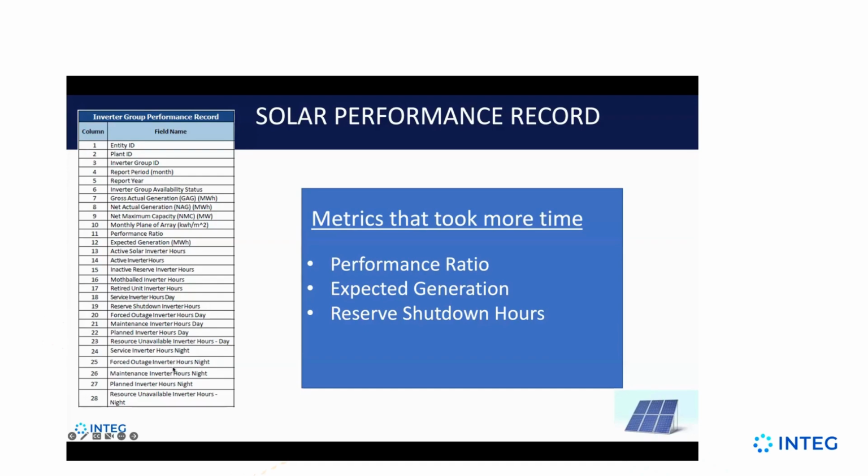A lot of folks, when they're doing their work, they're only looking at the outages when there's daylight out, and they're looking at the irradiance, but that's actually incorrect. You will have to look at what's going on at night. Especially if you had something that started, well, at night it doesn't matter, right? Because there's no sun, but you have to actually continue that outage.